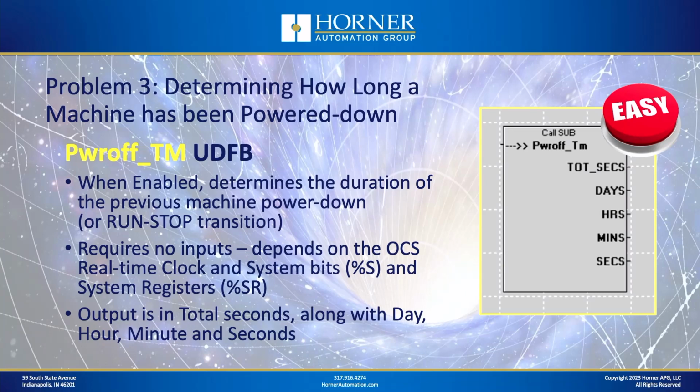So this power off time UDFB, one of the interesting things about it is that it doesn't have any inputs. You just connect it to the always on contact in your logic. There are no other inputs, and it will tell you the duration of the previous power cycle before the unit powered up this time. It doesn't have any inputs because it takes advantage of the real-time clock and other system bits and system registers to make this calculation.